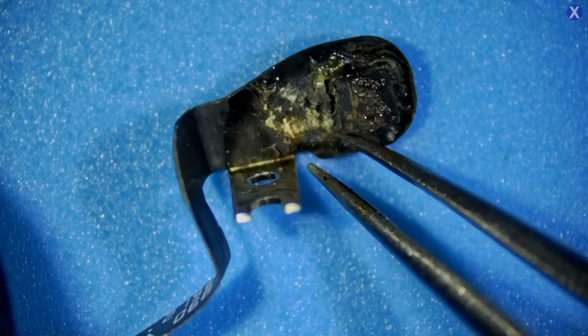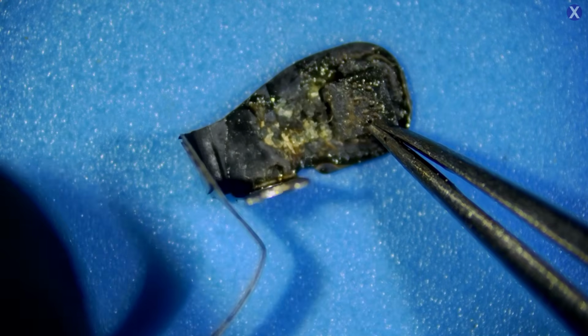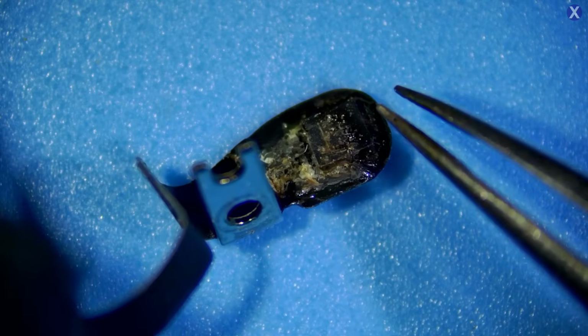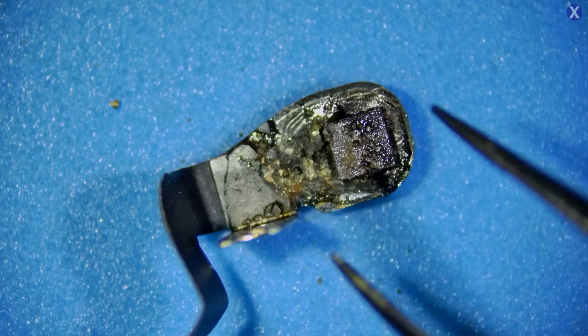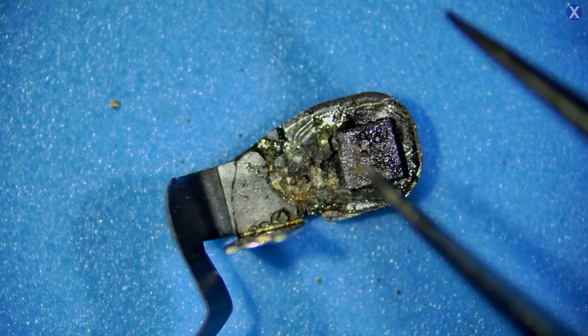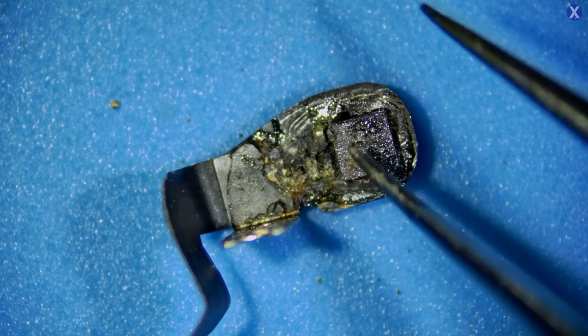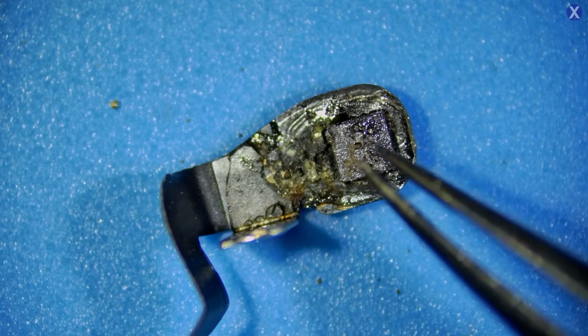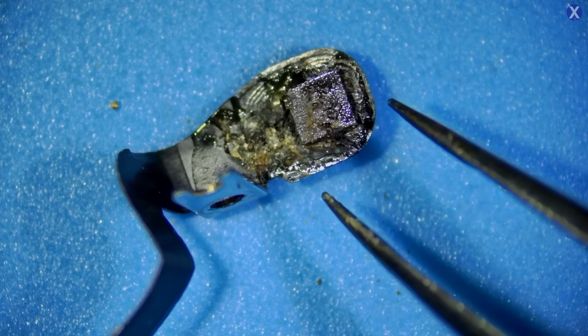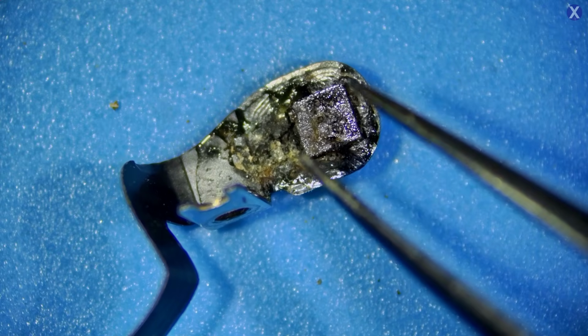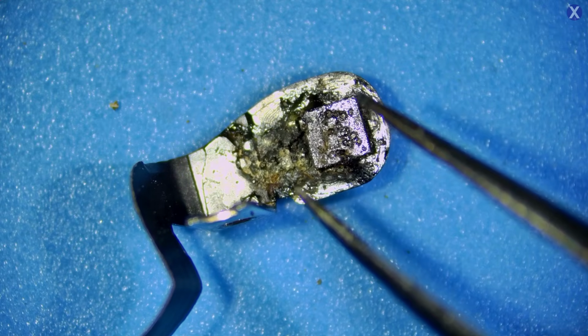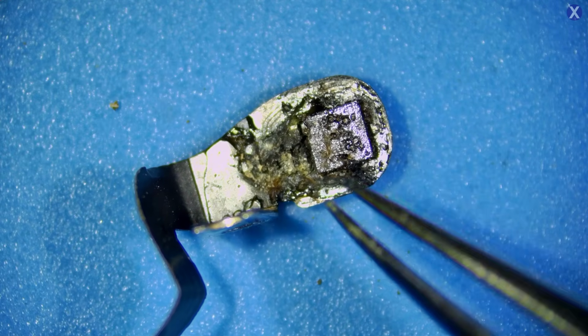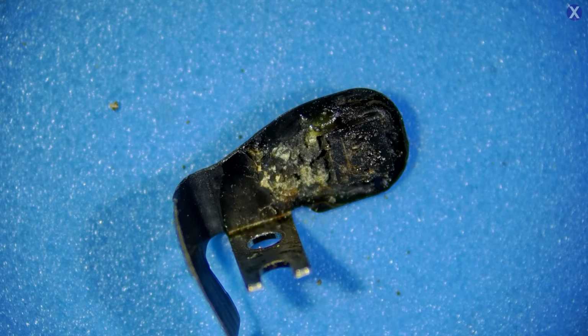The whole cable looks to be gone. It's very, very bad. And the corrosion looks horrendous here. There are components and there is a cable, right, that aren't too necessary. But what is necessary is this chip here, because this chip is what's calibrated. I don't think a cleaning will be good enough, just the amount of excess damage and just dirt and debris, everything that's there. So I don't really want to be using this cable anymore. So what can we do? When you have a cable this damaged, I don't want to be using it anymore.